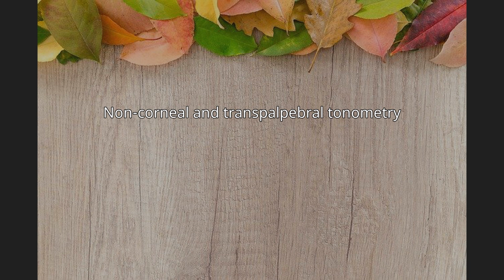Non-corneal and transpalpebral tonometry. Transpalpebral tonometry refers to methods of measuring intraocular pressure through the eyelid. The Diaton non-corneal tonometer calculates pressure by measuring the response of a free-falling rod as it rebounds against the tarsal plate of the eyelid through the sclera. The patient is positioned so that the tip of the device and lid are overlying sclera. Non-corneal and transpalpebral tonometry does not involve contact with the cornea and does not require topical anesthetic during routine use.